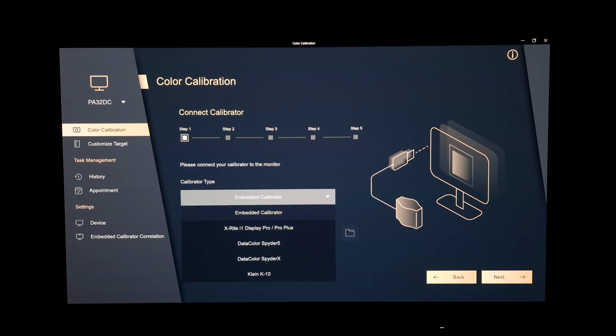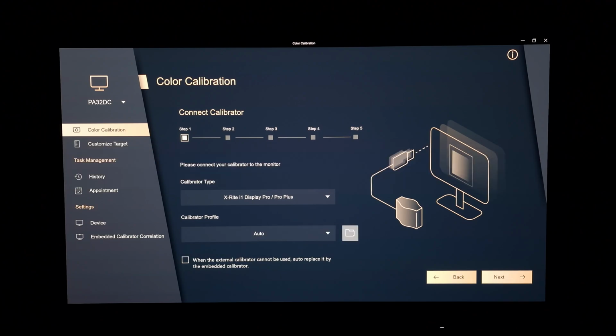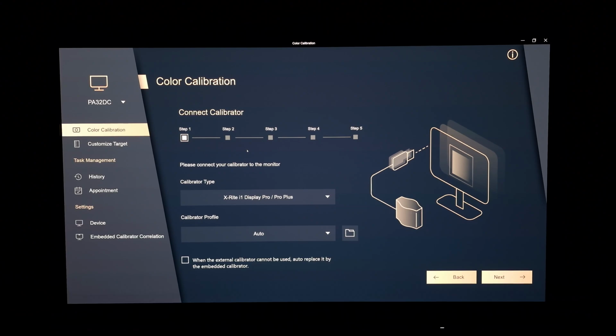other devices. And if you select the X-Rite i1 Display Pro or Pro Plus, also be aware that there's a calibrator profile option. What this allows you to do by pressing the folder icon is load an EDR file. Some people may be familiar with them. You can usually find them just floating around on the internet. People create them. And what this does is it basically adds some corrections to the colorimeter based on the backlight or the light source of the monitor, so it can be more accurate, more tuned to the spectrum, so that would potentially improve the accuracy of the adjustments made. I wouldn't fuss too much about this in general. I think you're going to get really good results even without this with most displays anyway.